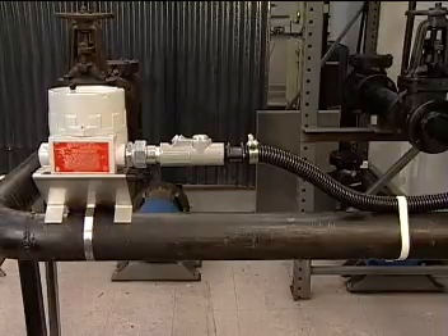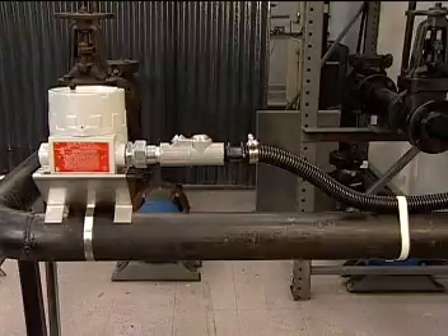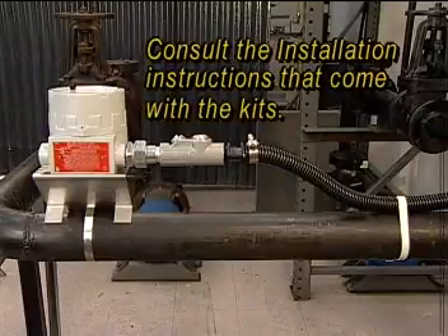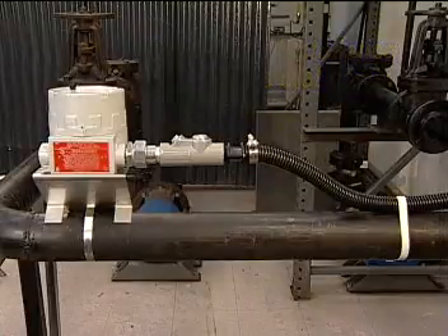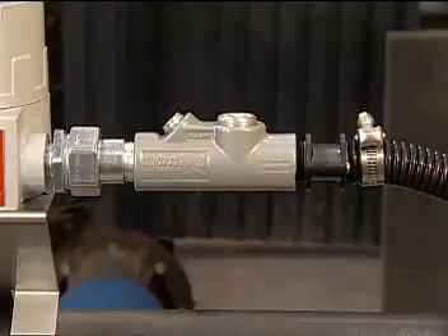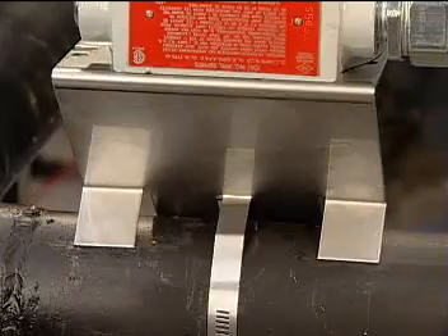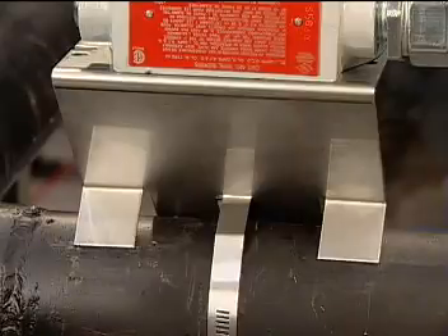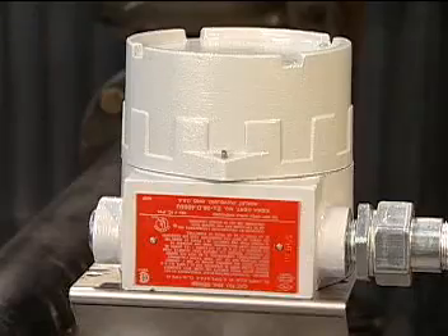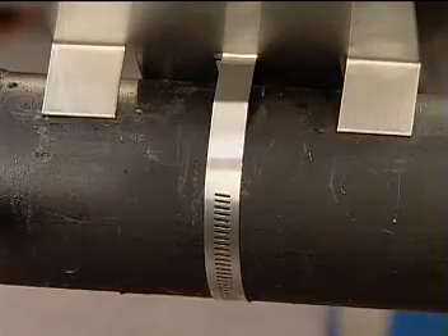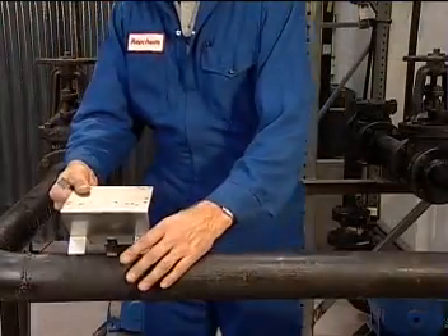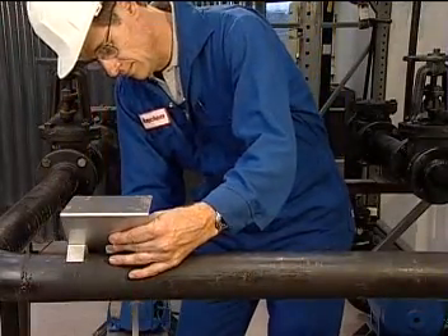Splices, T's, and end seals are installed in a similar way. Consult the installation instructions that come with the kits for installation of all these components. Remember that the mounting bracket and junction boxes are ordered separately. A complete power connection system contains the HAK C100 kit, Universal Mounting Bracket or UMB, JB3 junction box, and pipe strap. Make sure you leave 3 feet of extra cable to make the termination and service loop.